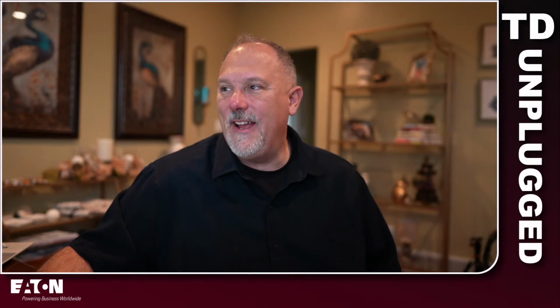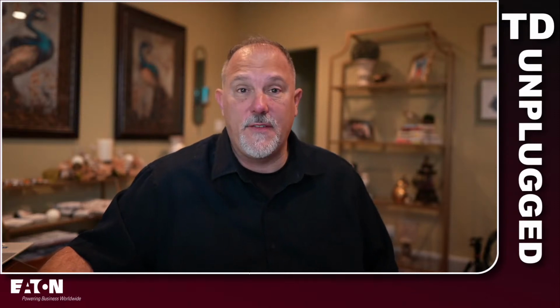Okay. Yeah, and we said the same thing. So overhead conductors and underground service conductors have the same language in it. So what's the third one? Part 4 is service entrance conductors. Let's take a look at the minimum size and ampacity. That's 230.42. Now this one's a little bit more complicated. It says service entrance conductors have to have an ampacity not less than the maximum calculated load to be served.